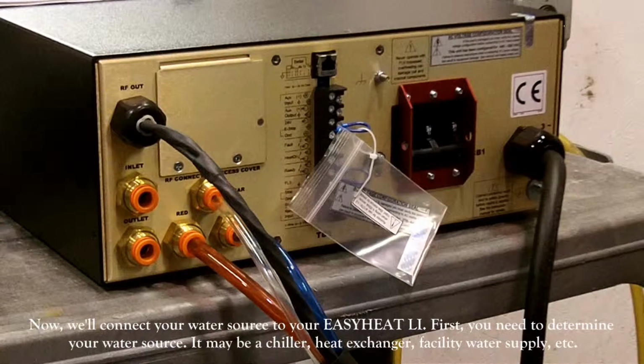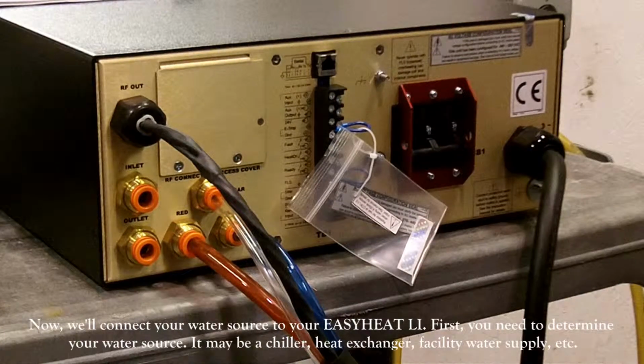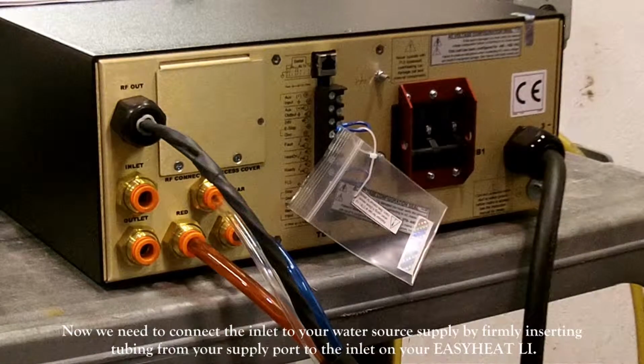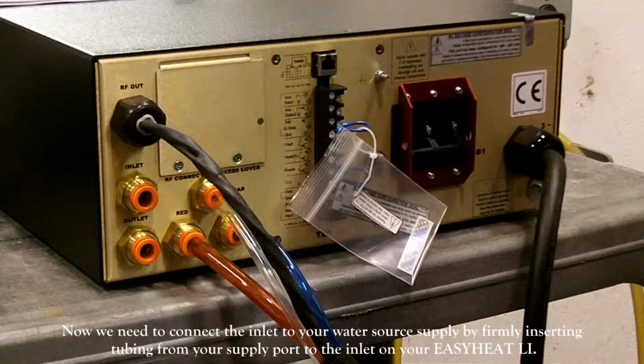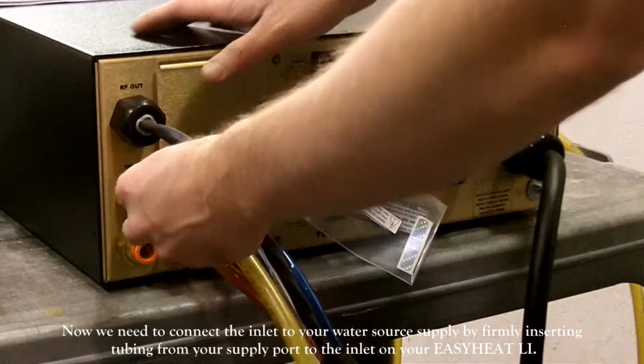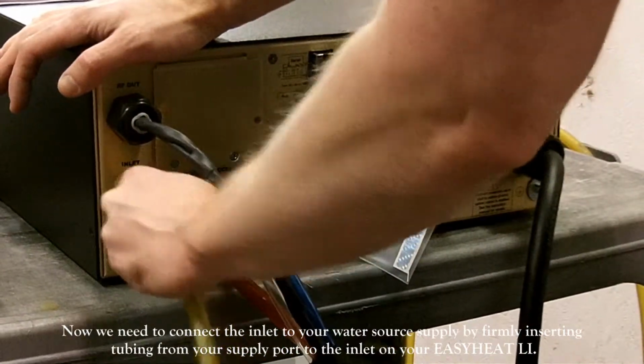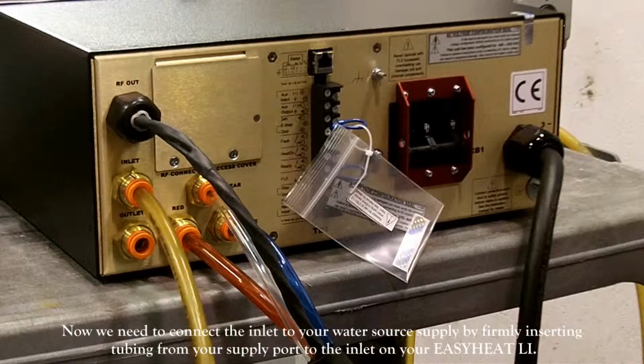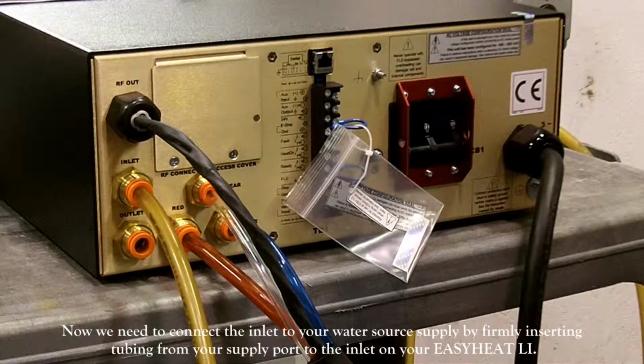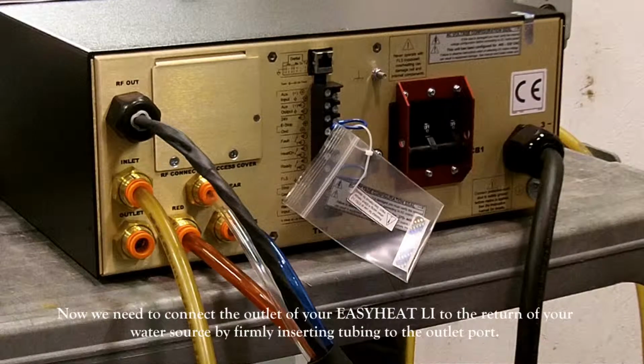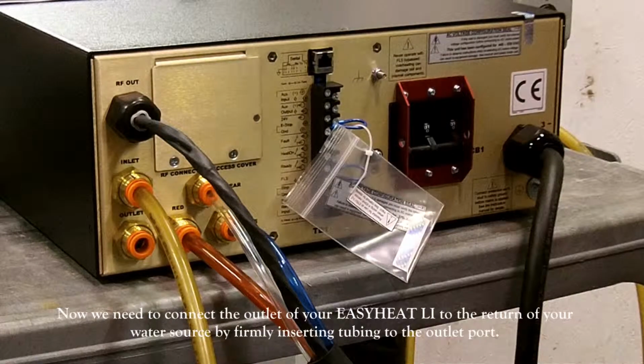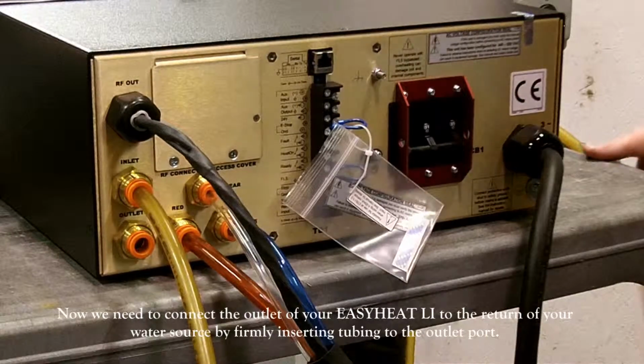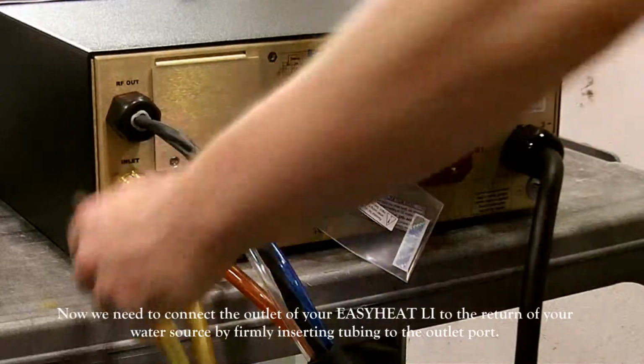Now, we need to connect your water source to your EASYHEAT LI. First, you need to determine your water source. It may be a heat exchanger, chiller, facility water supply, etc. Now, we need to connect the inlet of the EASYHEAT LI to the supply of your water source by firmly inserting tubing from your supply port into the inlet on your EASYHEAT LI. Now, we need to connect the outlet of the EASYHEAT LI to the return of your water source by firmly inserting tubing into the outlet port.